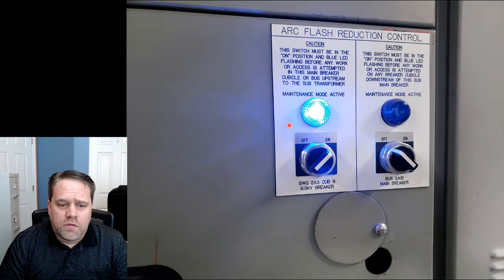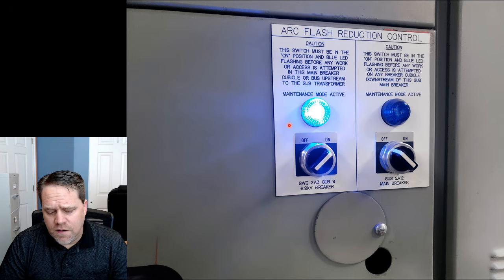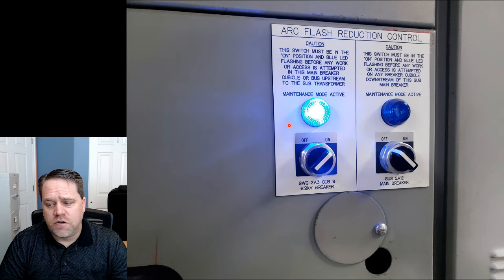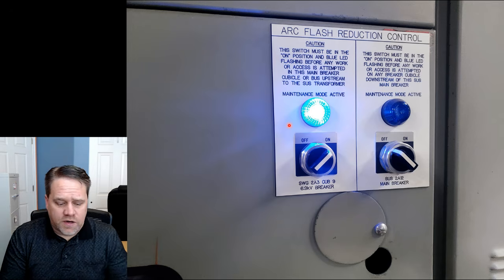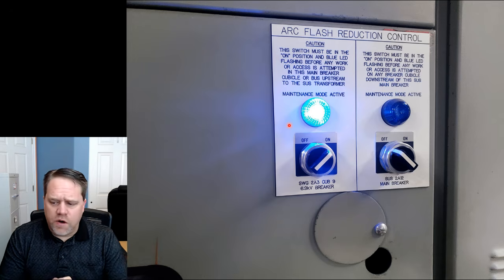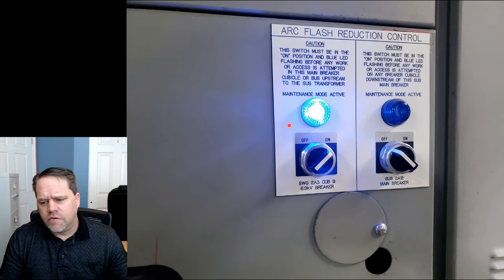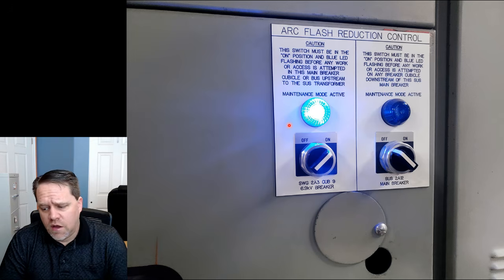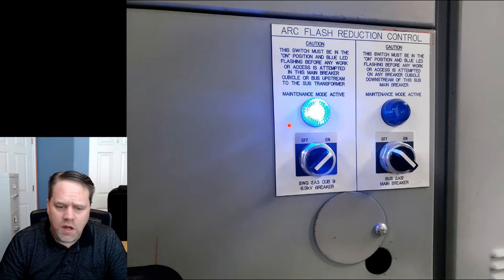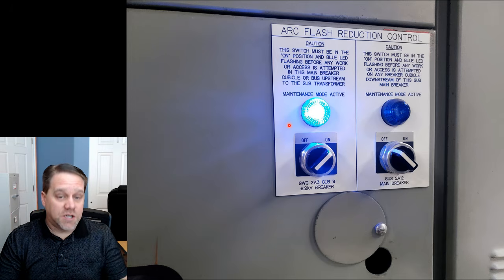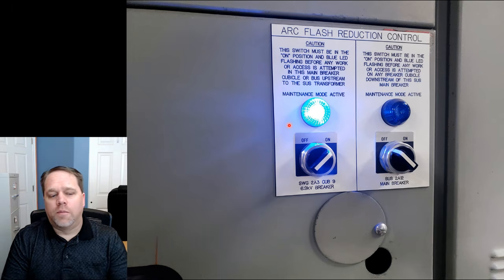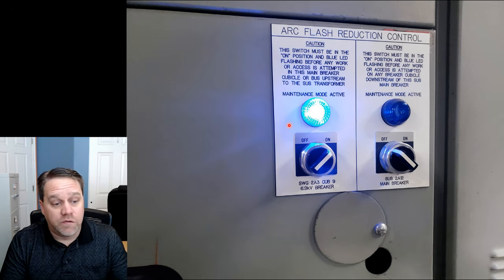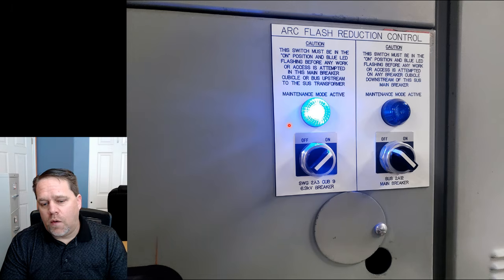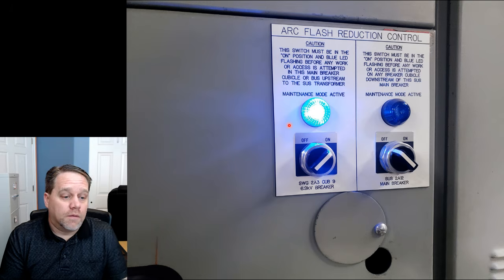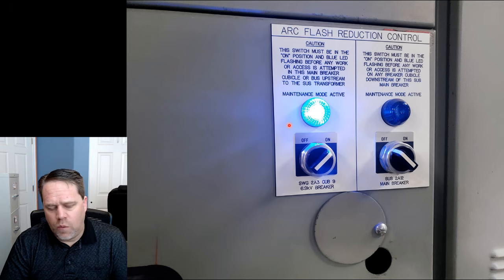This is some arc flash reduction maintenance switches. The idea here is that at a power plant, there are a lot of locations where you have to work energized. In most facilities, there's no reason to work energized — if your world is 120/208, 120/240, or 277/480, there's very seldom a legitimate reason to work energized. It's an OSHA violation, an NFPA 70E violation, and a good way to get yourself killed. You can shut down pretty much anything, except if you're in a power plant. If you shut something down there, you might cause millions of people to lose power, and many of those people depend on electricity for a life safety function — shutting it off could quite literally kill multiple people. So you have to work energized at a power plant.